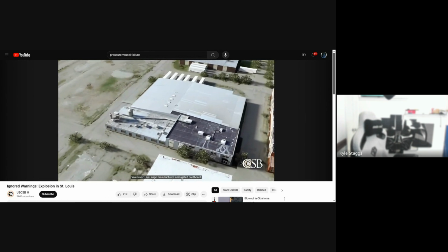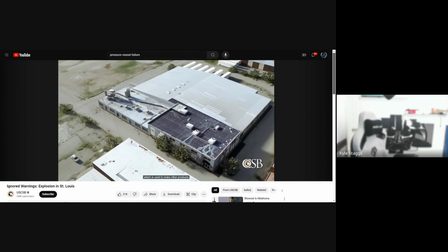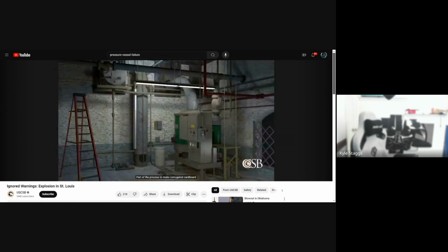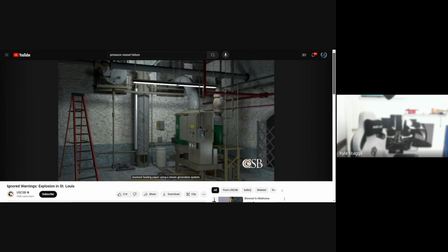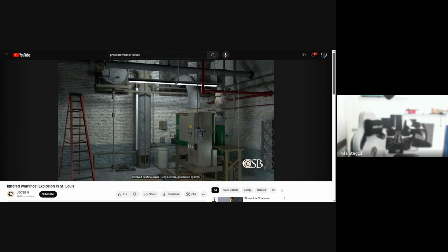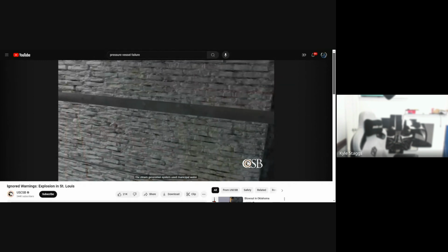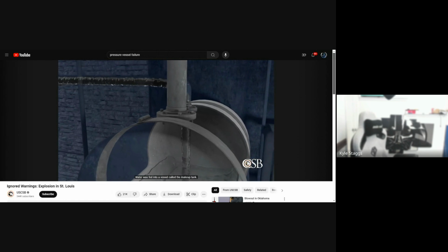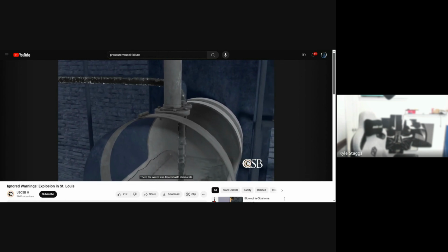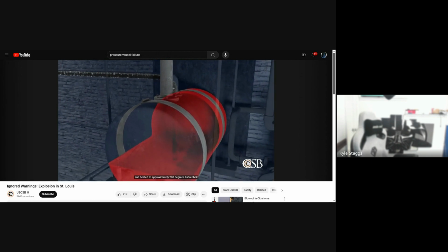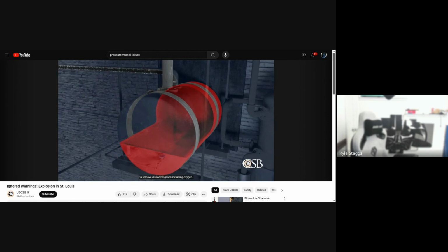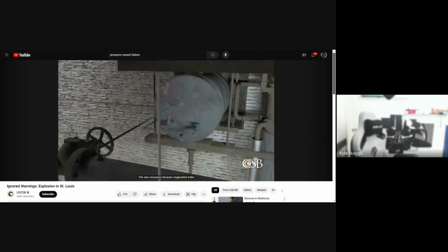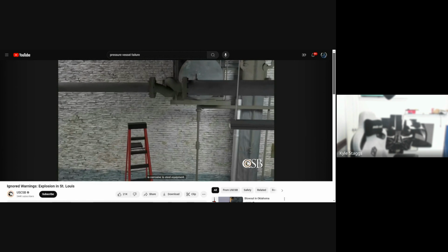Loy Lang manufactured corrugated cardboard, which is used to make other products such as boxes and retail displays. Part of the process to make corrugated cardboard involved heating paper using a steam generation system. The steam generation system used municipal water. The water was fed into a vessel called the makeup tank. There, the water was treated with chemicals and heated to approximately 200 degrees Fahrenheit to remove dissolved gases, including oxygen. This was necessary because oxygenated water is corrosive to steel equipment.